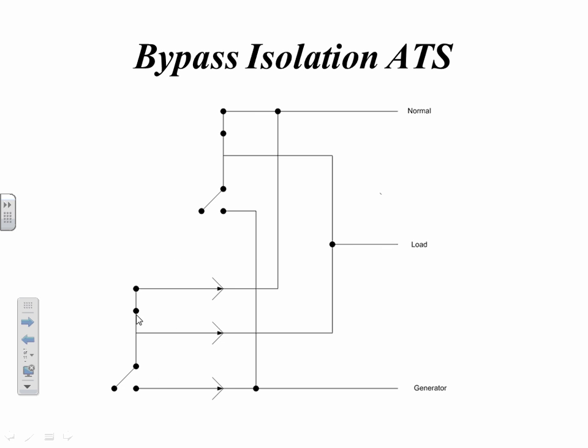So there's a problem with this transfer switch. It can actually be taken out. Now we're dealing only with a manual switch. Normal power was coming in here to the load. Now we've got an operator that can go out to that switch. He's already taken the automatic switch, or no, he's left it there. He might rack it out and get it away from this thing. So now he's taking the manual switch and he's changing it from normal and closing this switch to the generator right here. So a generator can supply power now up through this manual switch to the load. And it doesn't require a lot of time, but it does require a manual operation.